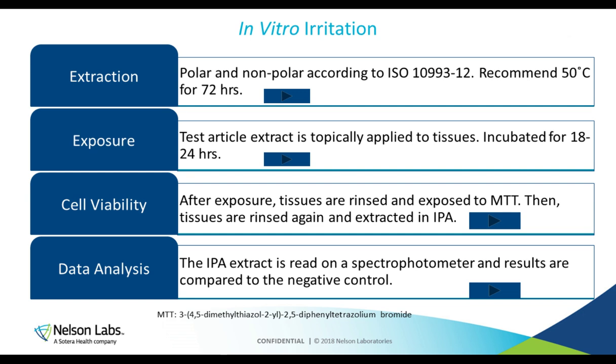And then if we go over to the chart, the graph, we see that our positive control is coming out very low, and we can interpret that all the way across. Our negative controls and our test articles came out as non-irritants. On the chart, I don't know if it's coming up very clear, but the 50% line is red. That's our indicator of where we're crossing between irritant and non-irritant status. This has been established by the testing performed and is outlined in OECD 439, where if you are below 50% viability, so you had a significant amount of cell death, we are saying that's an irritant, category 2 irritant.